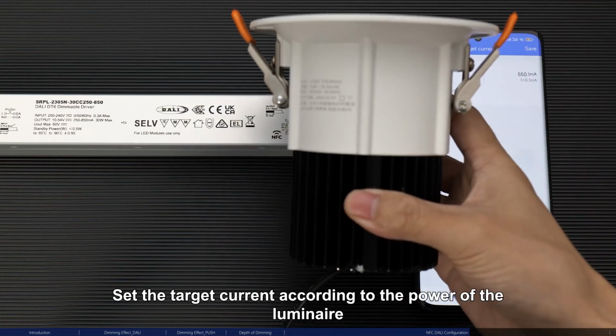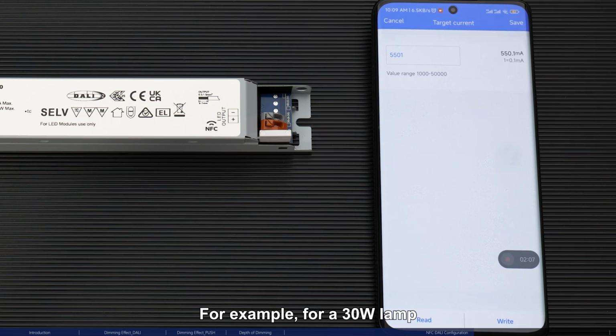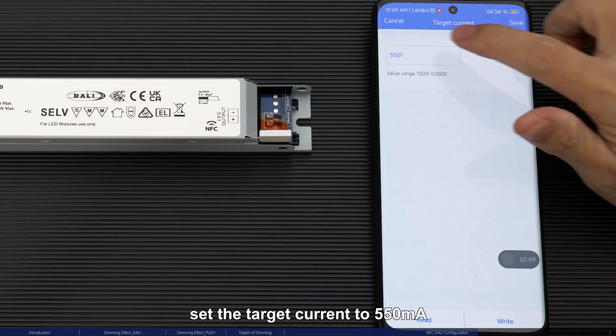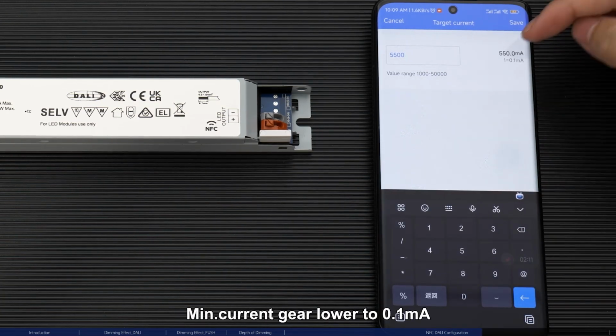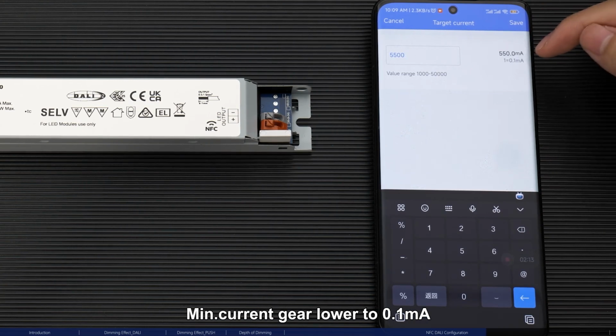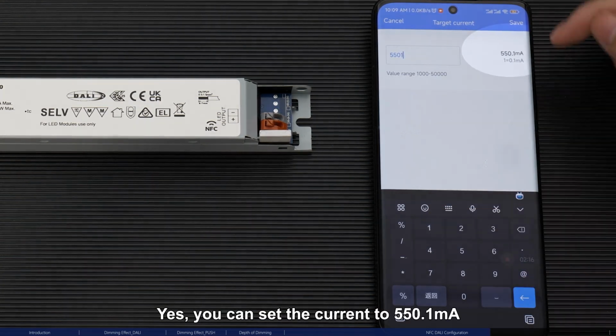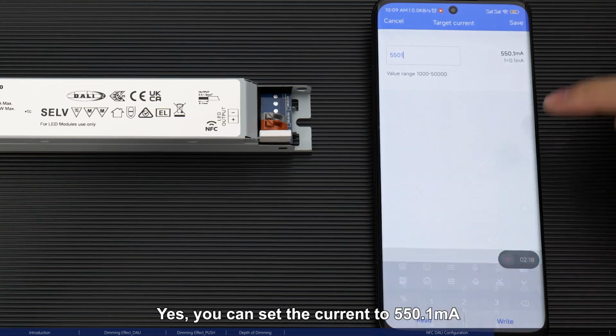Target current. Set the target current according to the power of the luminaire. For example, for a 30 watt lamp, set the target current to 550 milliamperes. Min. current gear lower to 0.1 milliamperes. Yes, you can set the current to 550.1 milliamperes.